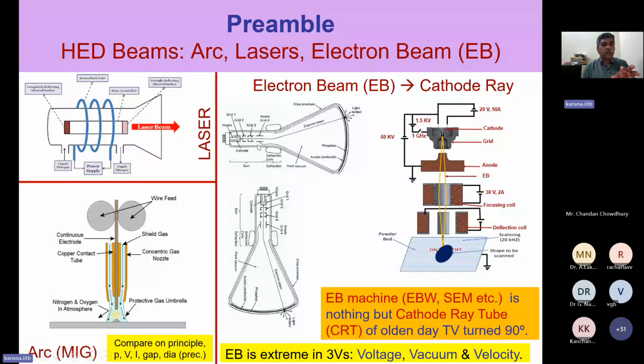And I told you the values of this. In this case, we minimum use 60 kilovolt. Okay. Let's say the wattage is almost the same. Let's say a 4 kilowatt or 12 kilowatt. When you use this 60 kilovolt, for 4 kilowatt, it will be 66 milliampere. For 12 kilowatt, it will be 200 milliampere. So here we are dealing with kilovolt or thousands of volt and milliampere current.